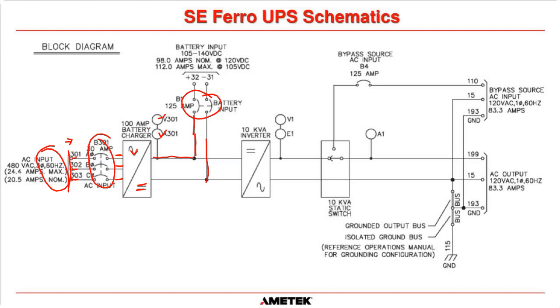Okay, and once again, at the top here, it tells you what our expectations are. And our expectations are that the battery can be between 105 and 140 volts DC on this system. So we know that it is a 60 cell, probably a VRLA or a VLA, a vented lead acid battery.